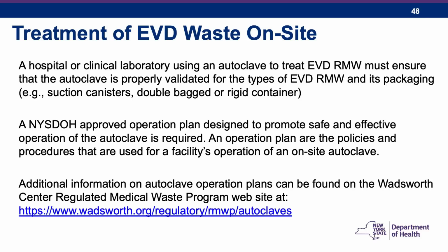So I just want to bring up requirements for autoclaves, and the CDC Ebola website includes information on survivability of Ebola virus and medical waste and includes suggested autoclave operating parameters. I just want everyone to be aware that those suggested operating parameters are less stringent than what is currently required by regulation by the New York State Department of Health. Our regulations, and I've included the specific sections of those regulations, describe the generally accepted and alternative operating parameters for autoclave used to treat regulated medical waste in New York State.